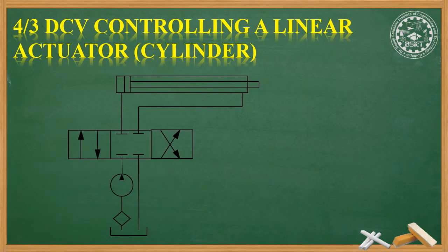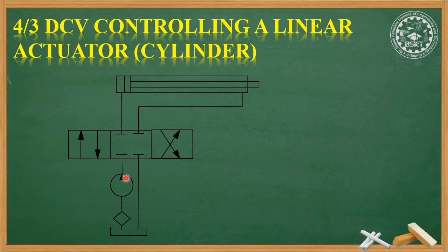Now let's look at a simple hydraulic circuit. This is a hydraulic circuit — we know it is hydraulic because all the triangles in the symbols, such as the triangle inside the pump and other component triangles, are solid (filled). If those triangles were hollow (unfilled), it would become a pneumatic circuit. This is a basic hydraulic circuit using a 4x3 direction control valve as one of its components.